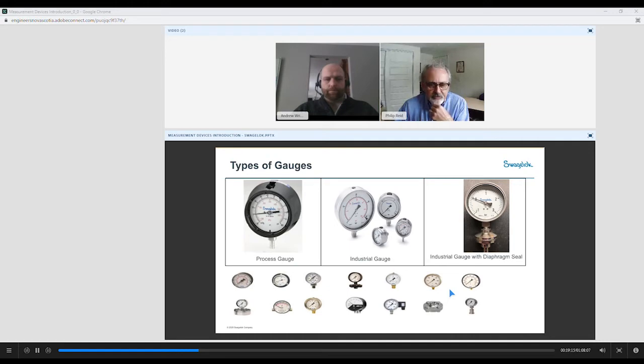These can have a crimped front, a bayonet mount front, so that you can get in to do calibrations on a lot of these gauges. If it has a crimped front, on the gauge, I apologize, I was pointing at this and I lost my pointer. But so the safety gauge blows out the back. The industrial gauges, being stainless steel, will again have different types of fronts. So that, as I mentioned, the bayonets are a screwed front.